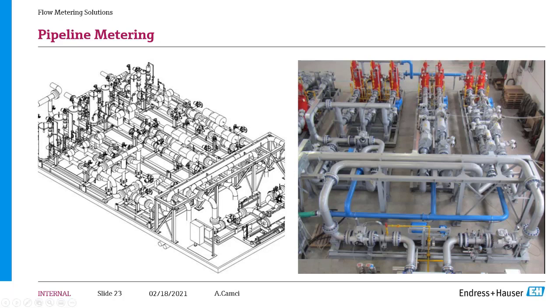But as this is a shared system, we have to ensure that the high pressure liquid is not leaking to the low pressure parts, because it will damage them. It is about their design pressure. Here we ensure the tightness of the system, and we also included safety valves and emergency shutdown valves, in case of leakage or misoperation, so that the high pressure liquid does not go to the low pressure side of the skid.